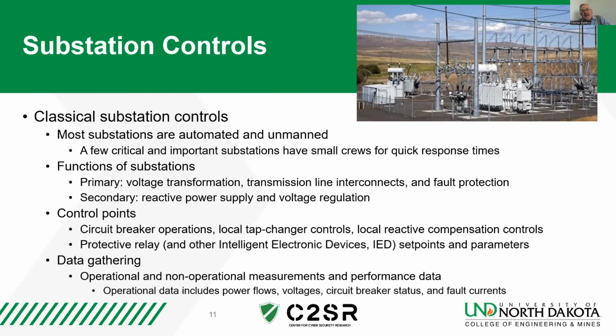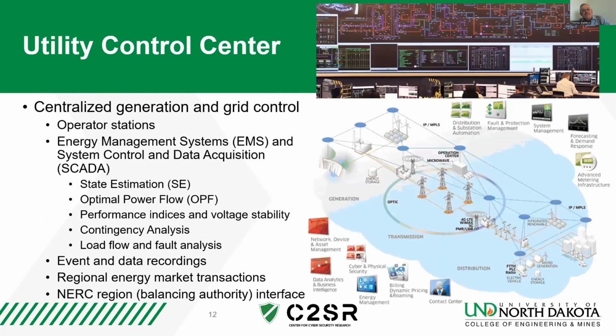Then the other important matter of substation is it's a major point of data collection where we monitor power flows, current levels, voltage values, and sending them back to the SCADA system. But also very important is the status of circuit breakers and tap changers on transformers, what are their current positions. That data goes back into the SCADA to the state estimator so that we have a good vision of what the state of the system is and having a good system model.